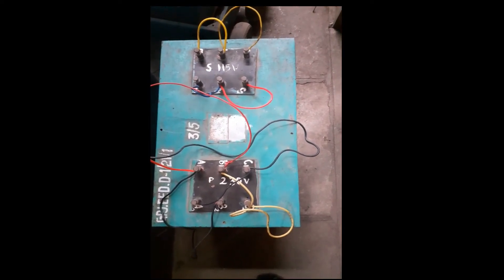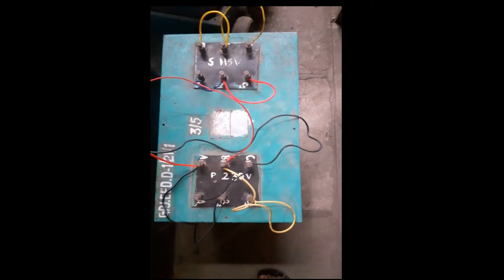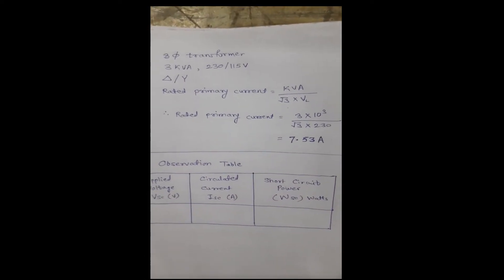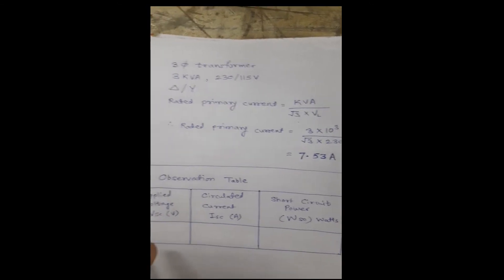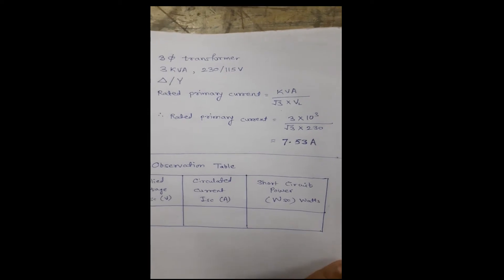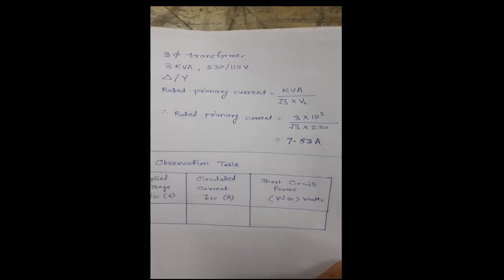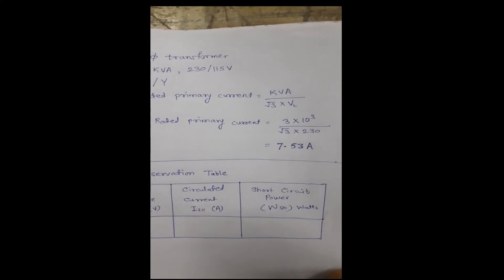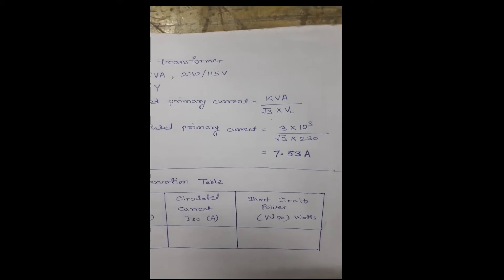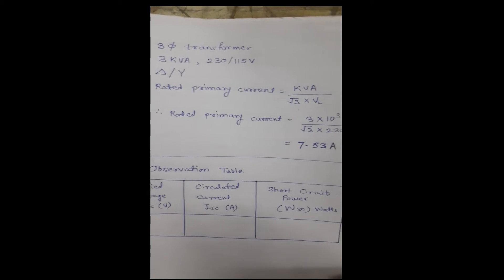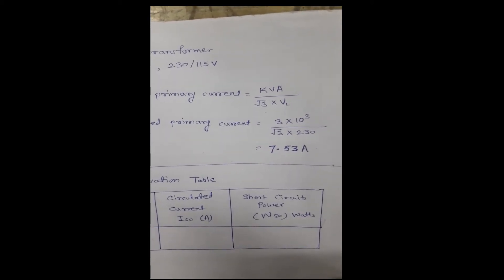As it is a short circuit test, the secondary terminals are short-circuited. For this 3 kVA three-phase transformer, to conduct this experiment we need to circulate rated current or a current below rated value during the short circuit. As per the given rating, the rated primary current is calculated for 3 kVA at primary voltage of 230 volts, giving a rated primary current of 7.53 amperes.